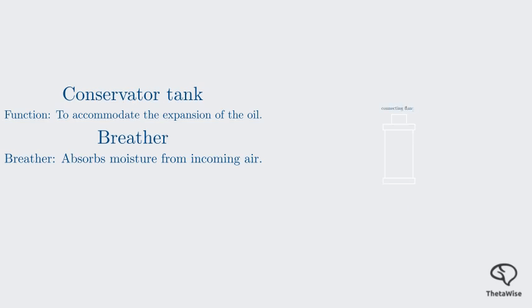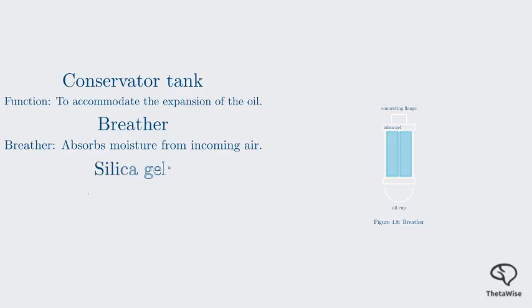It does this using a chemical called silica gel. Silica gel is a desiccant, which means it absorbs moisture. New silica gel is blue. As it absorbs moisture from the air, it turns pink, indicating that it's saturated and needs to be replaced or regenerated. The oil cup at the bottom of the breather prevents the oil inside the transformer from coming into direct contact with the atmosphere. Finally, for large and valuable transformers, a sophisticated protection system is used.